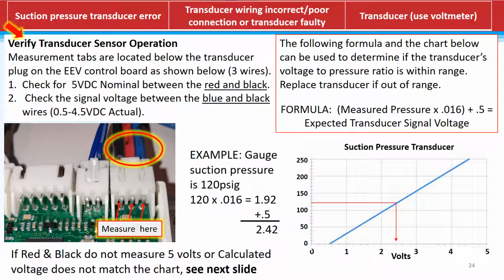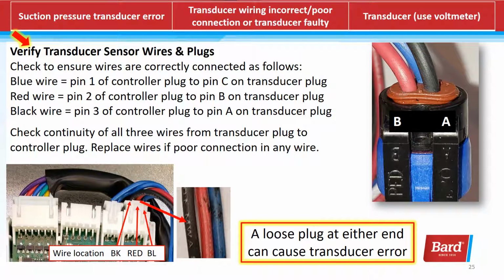If for some reason the voltage doesn't check out, then we're going to have to check out the wiring harness. So if the voltage didn't check out, we need to confirm the integrity of the connections and the wires. Use an ohm meter and check all 3 wires in the transducer harness for resistance and to see if they're shorted to ground. Replace it if it's defective. Also, as shown in the picture, be sure the wires are inserted in the right spot on the transducer plug and EEV board. If the voltage doesn't match the expected voltage, using the calculations on the previous slide while the wires check out good, replace the transducer. If you find a wire in the wrong spot on either end of the harness, replace the harness.